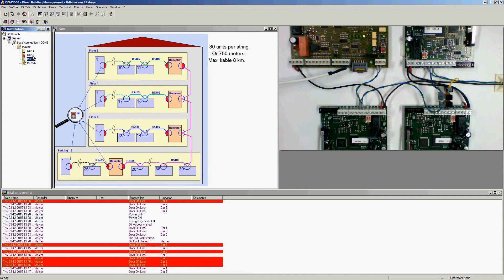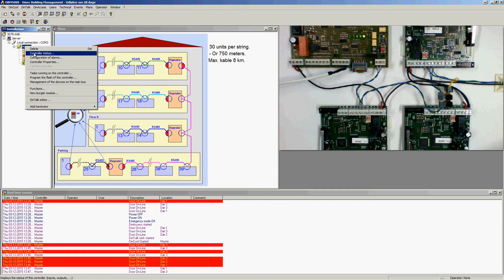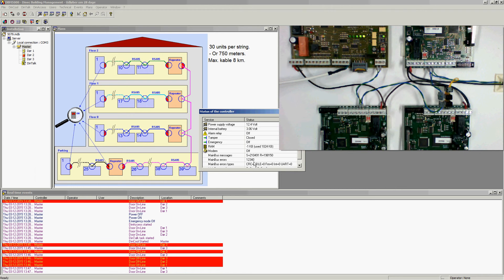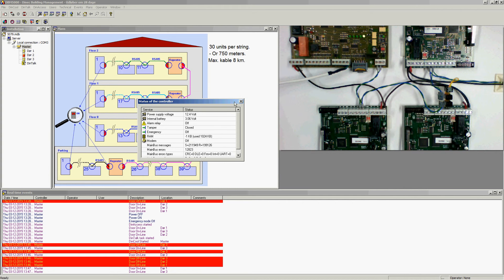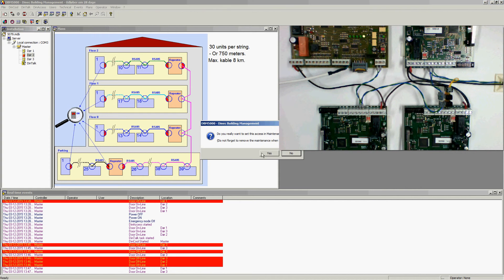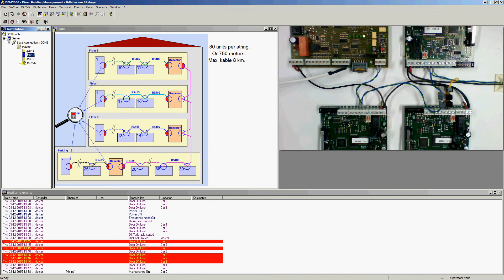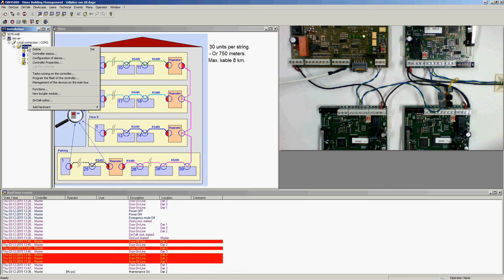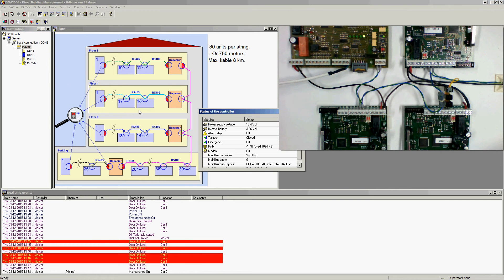But you can never be sure about that. So to check further doors, I would still have to press Ctrl+Shift, right-click, and ask for the controller status. You can see that my main bus error indicator is counting because the door is not responding to the hailing of the controller. I can shorten this door out by right-clicking and asking for maintenance. If I do that, no packages will be sent to the door, and I can now look at the controller status and see that my main bus error indicator is no longer counting.